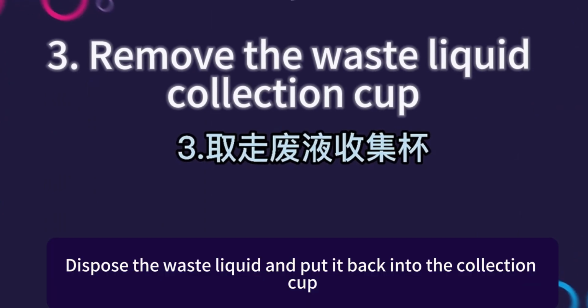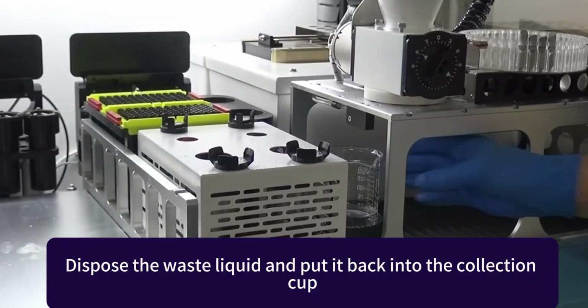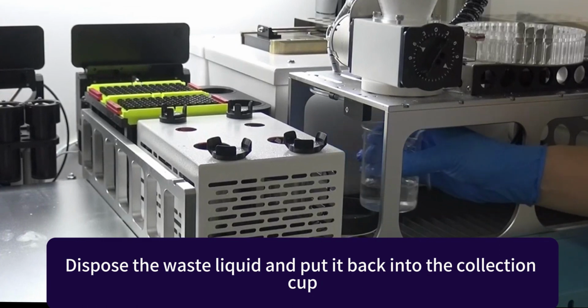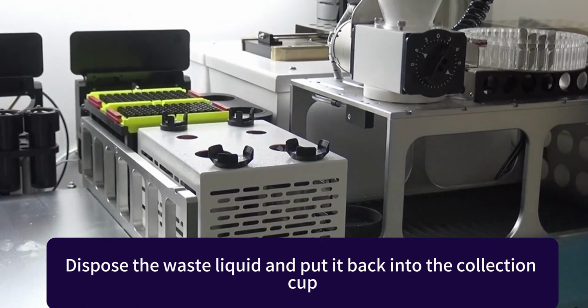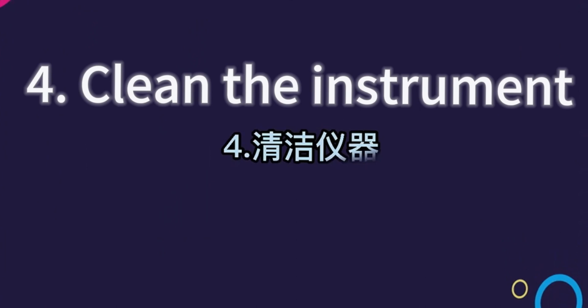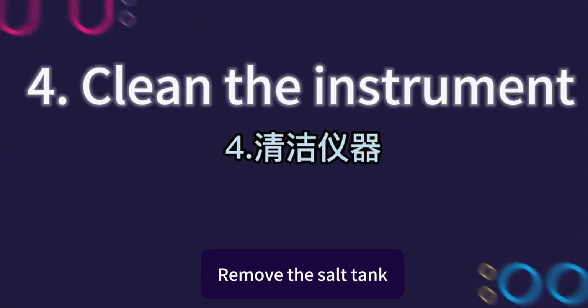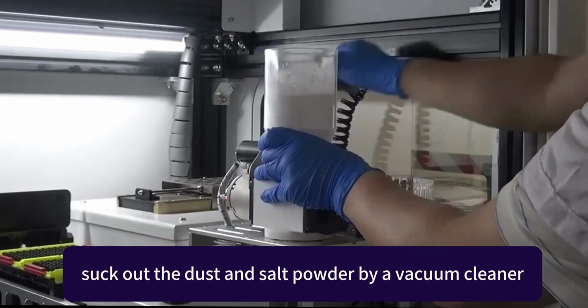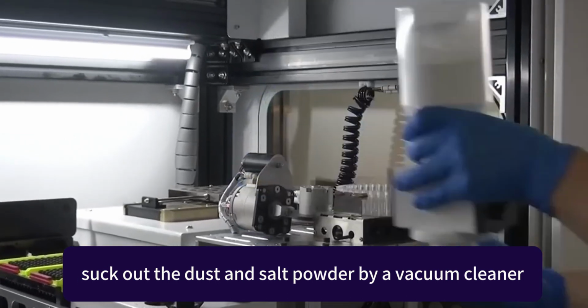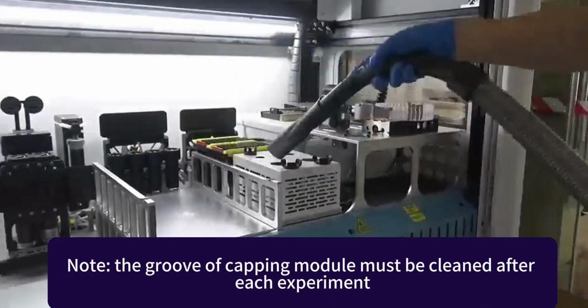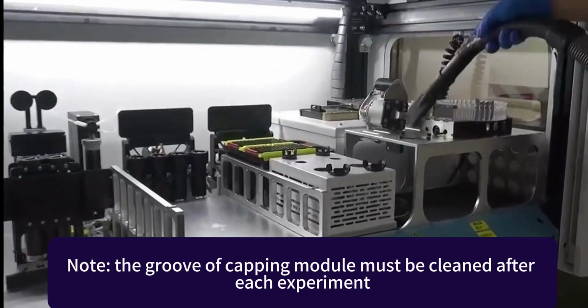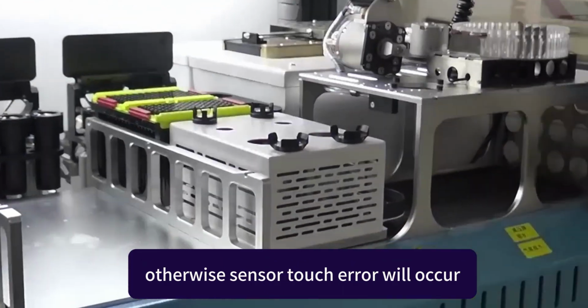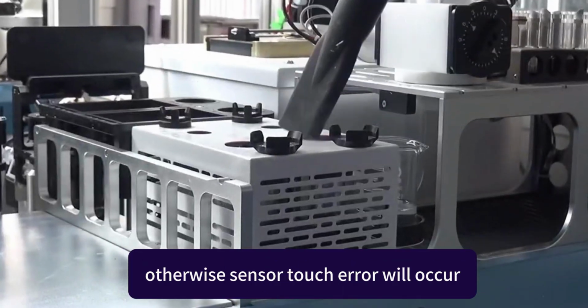3. Remove the waste liquid collection cup. Dispose of the waste liquid and put the cup back. 4. Clean the instrument. Remove the salt tank. Suck out the dust and salt powder with a vacuum cleaner. Note: the groove of the capping module must be cleaned after each experiment, otherwise a sensor touch error will occur.